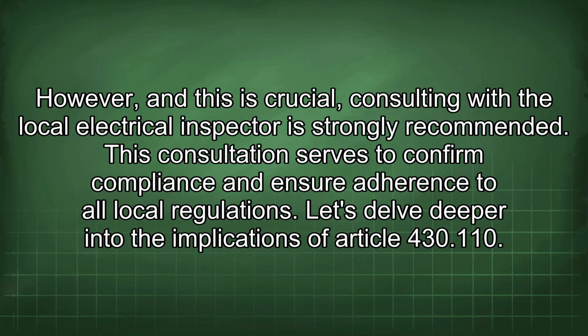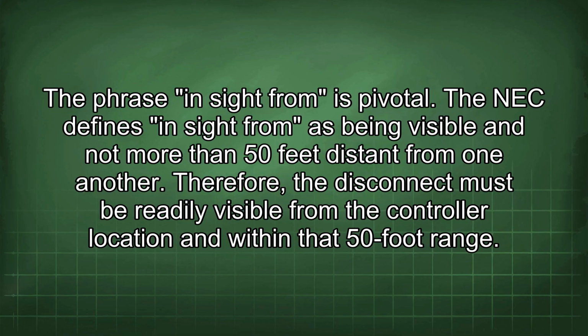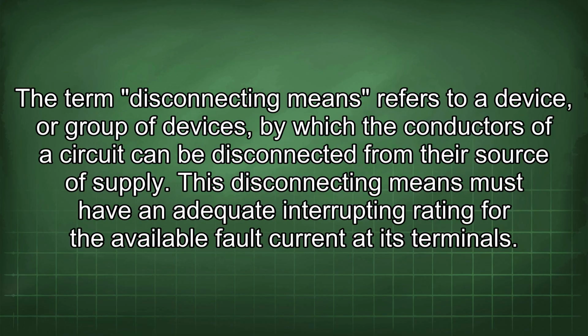Let's delve deeper into the implications of Article 430.110. The phrase "in sight from" is pivotal. The NEC defines "in sight from" as being visible and not more than 50 feet distant from one another. Therefore, the disconnect must be readily visible from the controller location and within that 50-foot range. The term disconnecting means refers to a device or group of devices by which the conductors of a circuit can be disconnected from their source of supply.